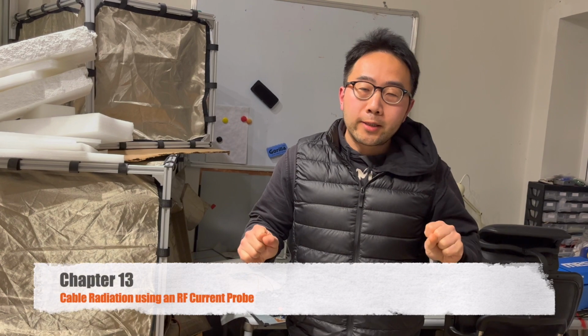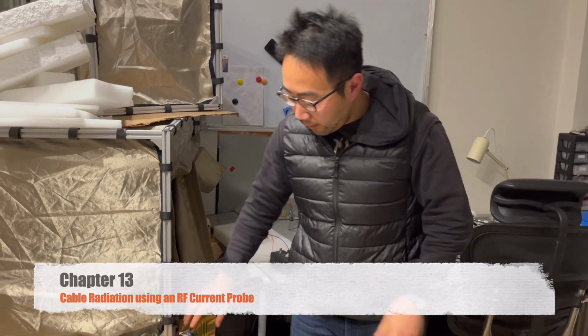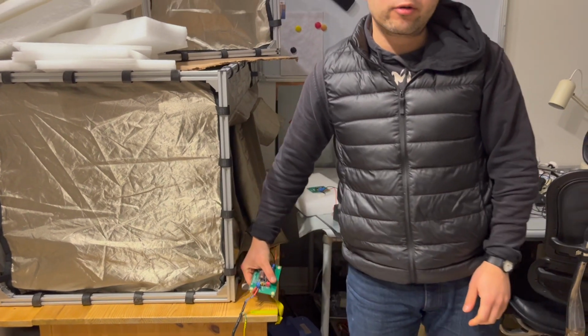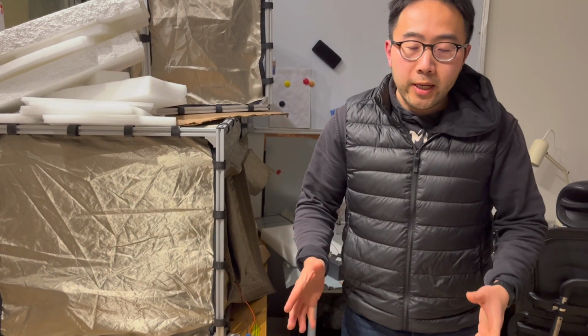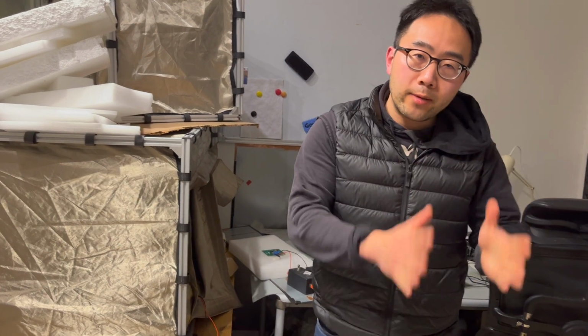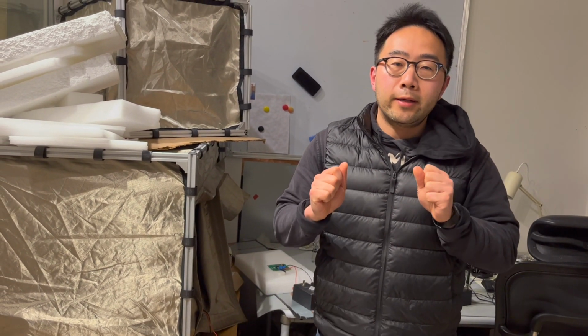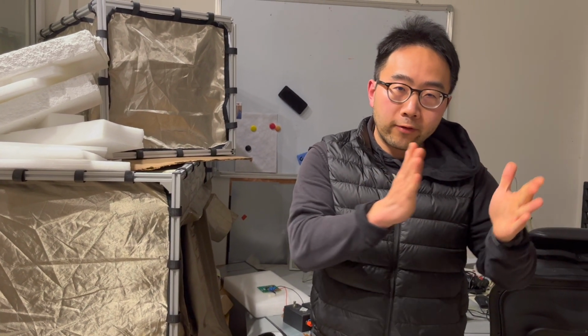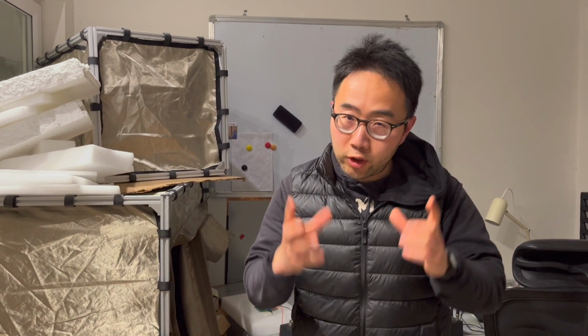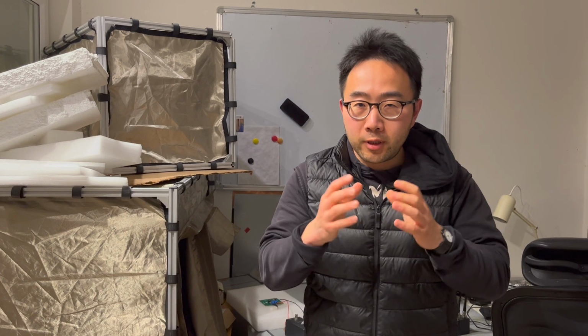Okay. We explained before that again we're using this AC-DC converter as a demonstration. We explained before that if you look at the TEMCell results and compare with the far field results, then you can see that in the sort of 30 megahertz up to about 70, 80 megahertz, the TEMCell cannot predict the radiation effectively. That is because for this particular product, pay attention, I said for this particular product, which is a power conversion board, the main radiation route is through the cable, right?